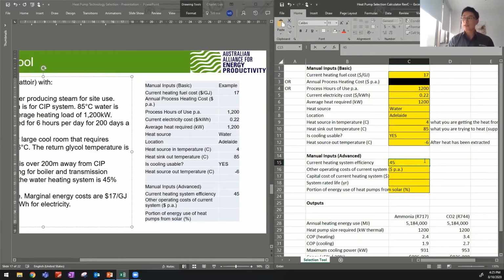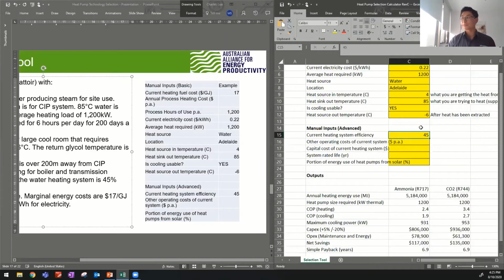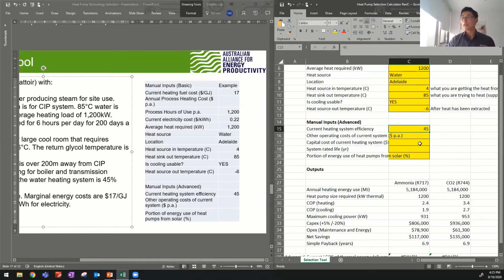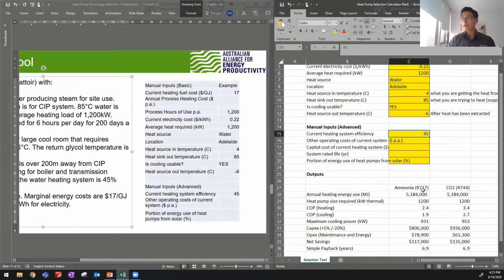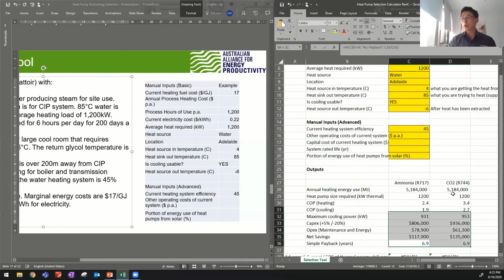If you're looking at LPG boilers and LPG replacement scenarios, which one of the questions did ask about, you would adjust the fuel cost to your LPG equivalent and your heating efficiency to an LPG boiler, which is about 70% max, and that's the only thing you'll change. So in this scenario, even with the low utilization, heat pumps would work fairly well. And in this temperature range, both heat pumps perform similarly.